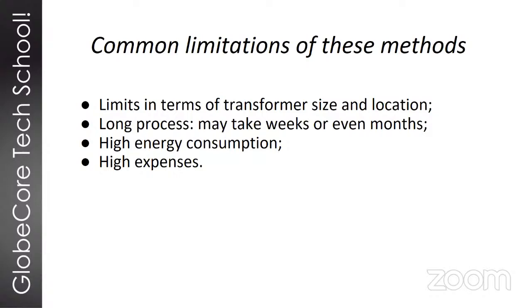However, if it's not possible to use this method for some reason, then the most important thing to be considered in the first place is whether the transformer tank can hold a vacuum of 0.1 millibar or less. So to dry insulation in transformers with tanks that can hold this vacuum, you can use just about any method from the table in the slide that we've shown, which does not require extraction of the core, regardless of whether the drying is performed in a shop or on site. And this is especially important for medium and large transformers, because it may be difficult to extract the core from their tanks.